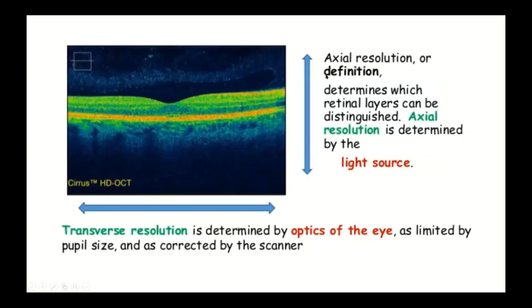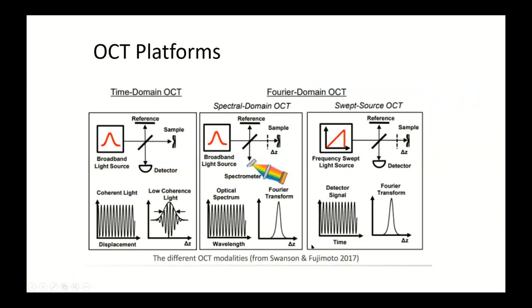One has to remember there are axial and transverse resolutions: axial resolution is determined by the light source, while transverse resolution is determined by the optics of the eye. The Fourier domain OCT is comprised of spectral domain and swept source OCT technologies. In the time domain system, a reference mirror moves to compensate for reflected light. In Fourier domain OCT, a fixed-position reference mirror is used, resulting in less movement, improved capture speed, and much better image quality.